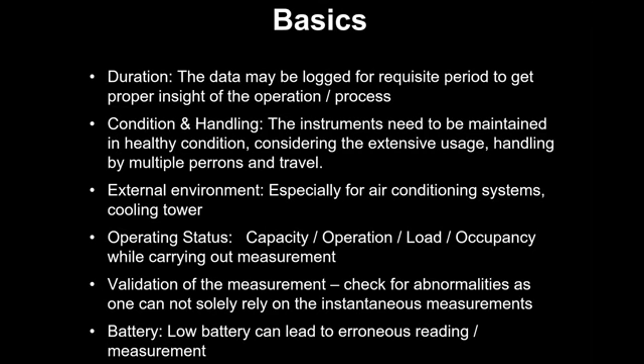Based on that, many times suggestions can be given. I'll tell you a case that happened. We were doing an audit for an office building, and we were doing logging for electrical parameters. What we observed during the 24 hours was that the office was running from maybe 9 o'clock to 7 in the evening. At night, it was a standard building, so some lighting, some security and the server room were on, and that consumes a certain power. So we carried out power logging for 24 hours.